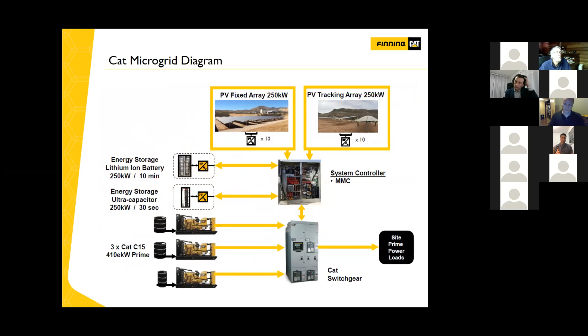This slide, I felt it was necessary to show everybody. For a remote site, it's very important to recognize that the PV inverters cannot be on the grid just by themselves. If the energy storage was not at site, you would always have to run at least one diesel genset, because the PV inverters are not grid forming. You need something there to actually regulate the voltage and frequency and set that. And in this example, we were able to shut off all 3 of the diesel generators because of that little bit of battery storage at site.